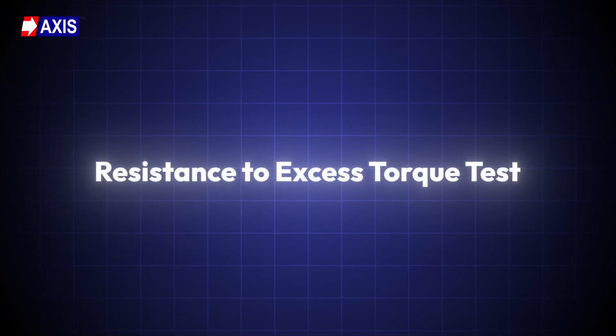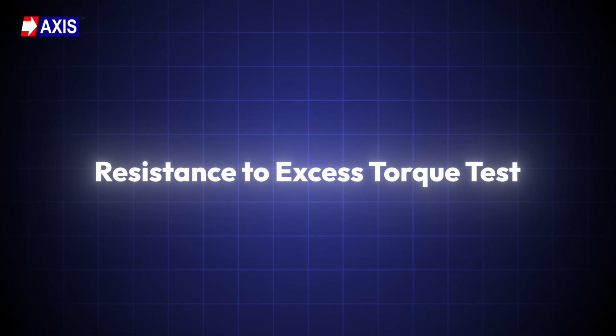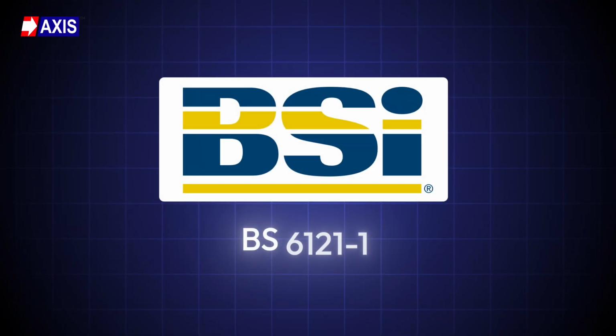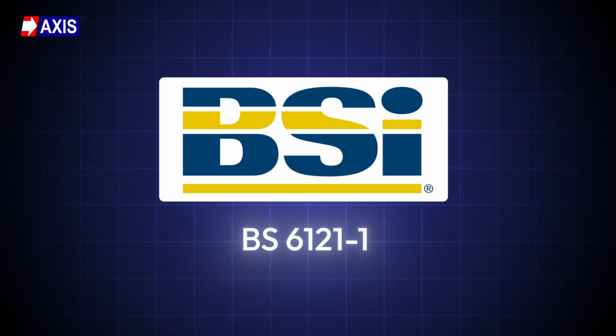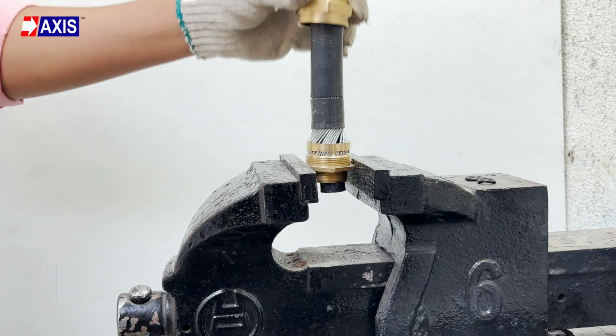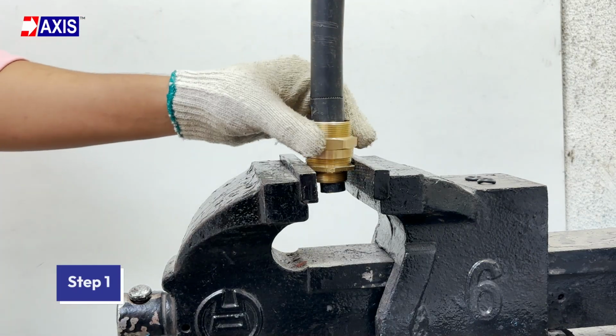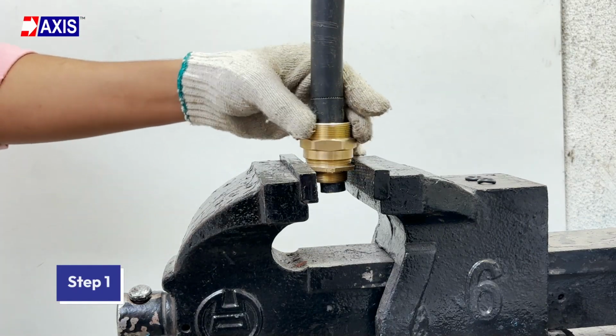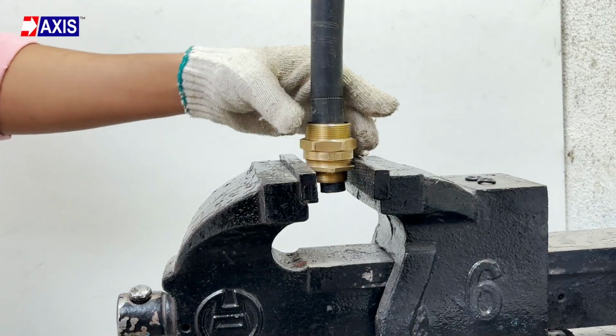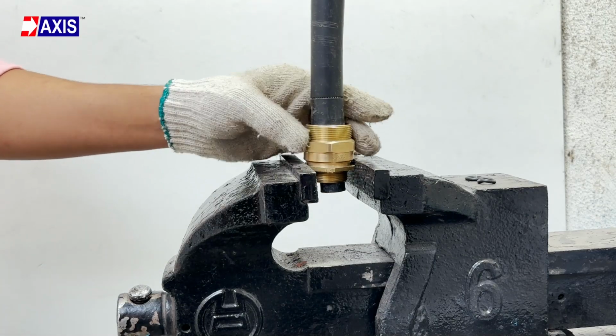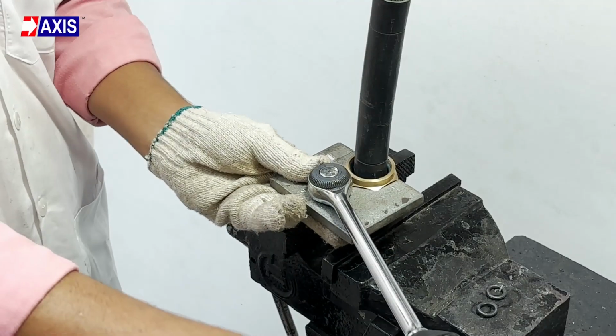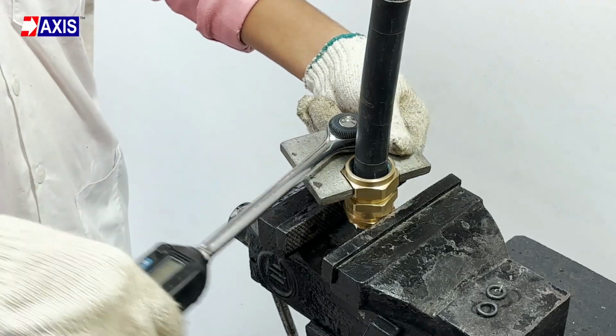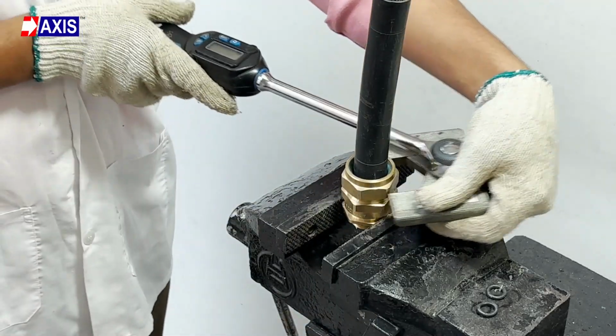Lastly, resistance to excess torque test as per BS 6121-1:2005. Step 1. Preparing the sample. Assemble the armored gland on a section of cable that has the largest armor thickness within its size range. Tighten it as per the manufacturer's standard installation torque.